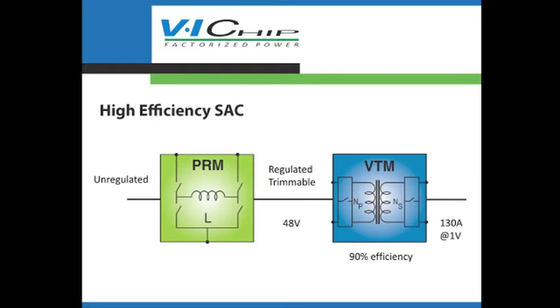This is a fixed-ratio isolated DC to DC transformer running on a fixed frequency, high frequency topology. Unlike traditional solutions such as a synchronous buck converter, the sine amplitude converter does not have any of the duty cycle limitations. So we can achieve very high efficiency conversion from 48 volts direct to 1 volt, for example up to 90% efficiency and 130 amps at 1 volt.